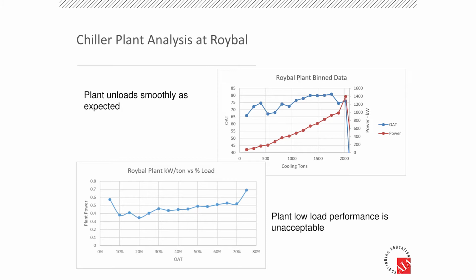This is the same data for just the Roybal building. This is where we're operating now. On the very high end, we're hitting 0.7, almost 0.7 kW per ton, which would normally be a flag in our monitoring-based commissioning platform. And at the really low end, we were hitting close to 0.6.